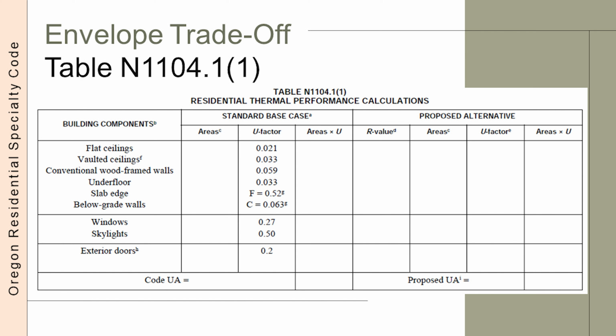So here is the trade-off spreadsheet table. You can see the standard base case columns with the prescriptive U factors already filled in. The customer fills in the appropriate areas, multiplies by the U factors, then the sum of the results are put into the code UA. Then the proposed alternatives are input. The R values of insulation to be installed, the areas for each assembly type, and the U factors are input into the table. Then the area times the U factors are put into the last column, and the sum of the design is input into the proposed UA box. The design meets code if the proposed UA is less than or equal to the code UA. So it lets in less energy than the code building.